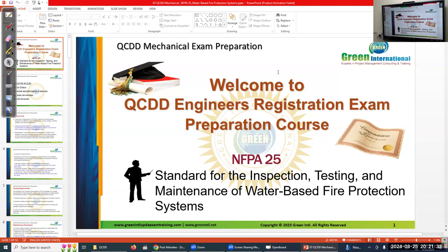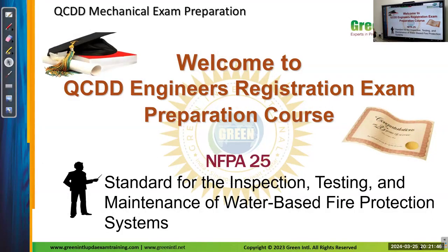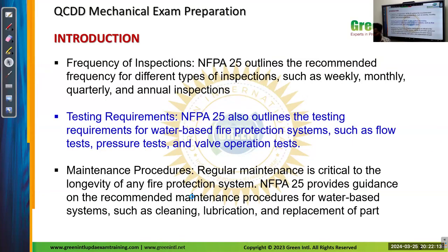So inshallah we'll start. So NFPA 25. In each NFPA code, as we discussed, there is a section for ITM, inspection, testing, and maintenance. For water-based fire protection systems, even in sprinkler systems or standpipe systems, all this ITM is commonly taken from this NFPA 25. If you go to NFPA 13 or NFPA 14 for the ITM section, they say the reference will be given to NFPA 25. Not all, but some references. The tables will be common for both of these. So if any ITM question is asked in the entrance exam, go directly to NFPA 25, otherwise it will be time consuming for you.